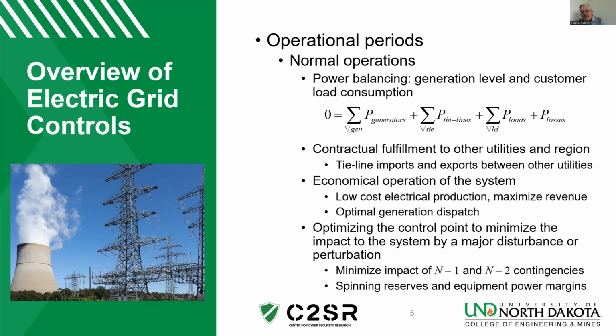Now, what's important is that it runs through a short-term load prediction, which uses both current data of weather and other events that are taking place for that particular day, and takes into effect the historical data of how much power was used the day before, or what was used in years past, and under what weather and other conditions. So historical data and current data are mixed together to come up with a prediction of how much power is going to be consumed by customers for the next 30 or 60 minutes. And under those constraints, what should the distribution of loading across the generators be? Or in other words, what should the set points of the output power of generators be to run the system efficiently?